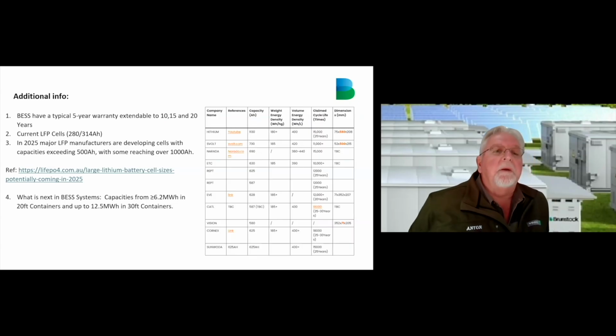So BESS have a typical 5-year warranty that's extendable to 10, 15, and 20 years. Current LFP cells that they use in most BESS systems today are 280 and 314 amp hour. In 2025, major LFP manufacturers are developing cells with a capacity exceeding 500 amp hour, with some reaching over 1000 amp hour per cell. There is a link that I have included that you can read more about it. And you can see in the table who the manufacturers are that are producing these new big cells.